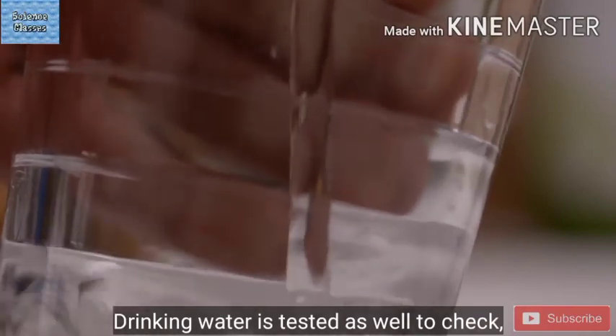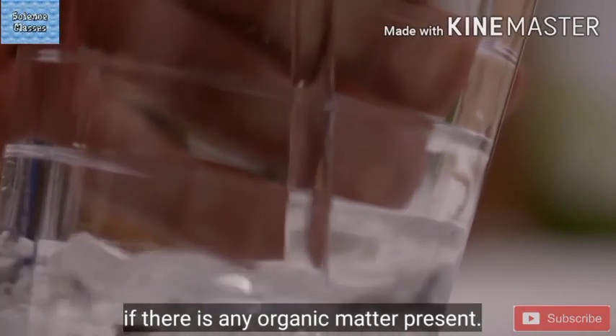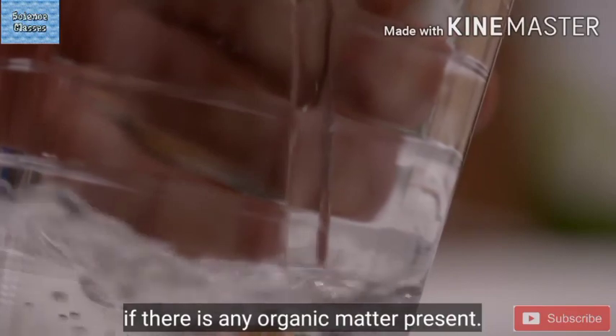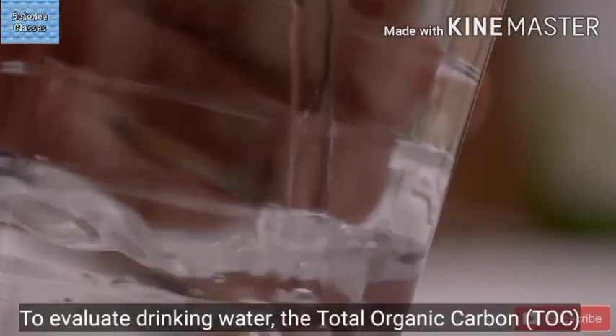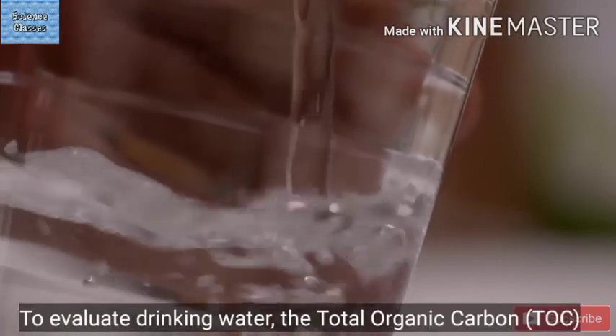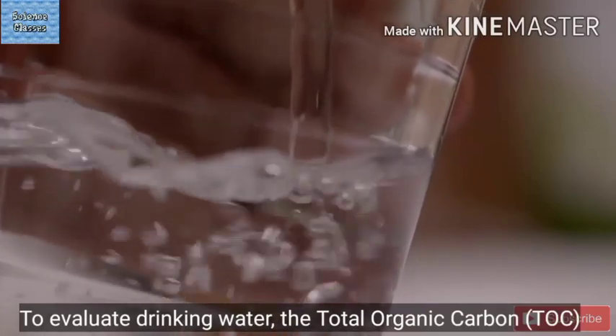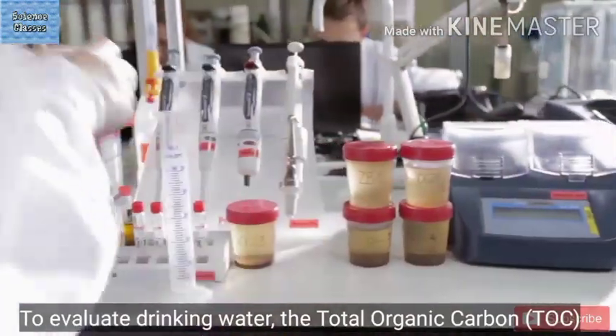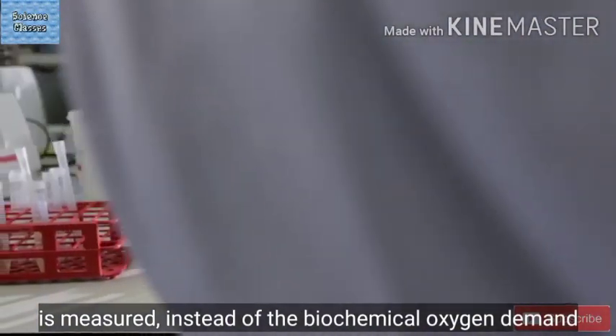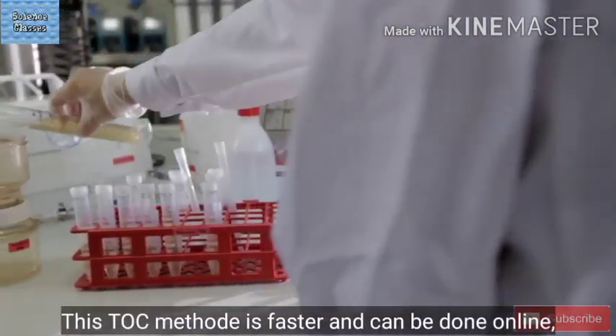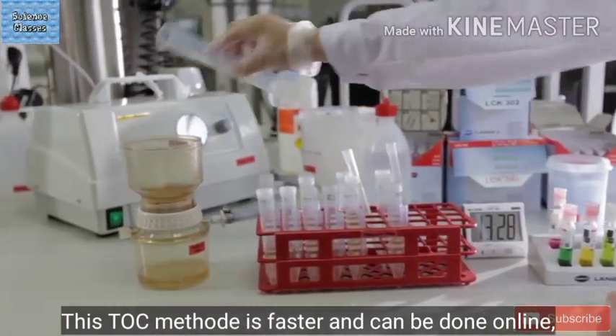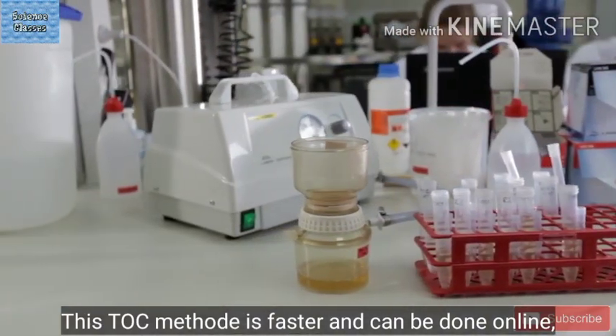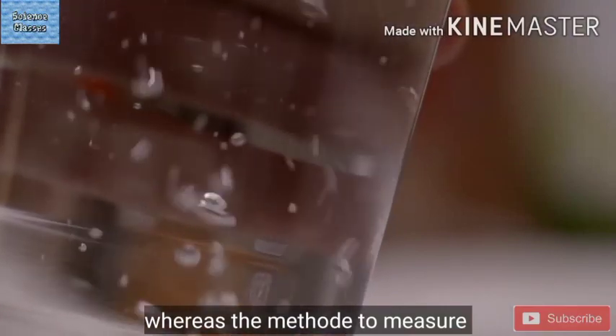Drinking water is tested as well to check if there is any organic matter present. To evaluate drinking water, the TOC, or total organic carbon, is measured instead of biochemical oxygen demand. This TOC method is faster and can be done online, whereas the method to measure the biochemical oxygen demand takes 5 days to get results.